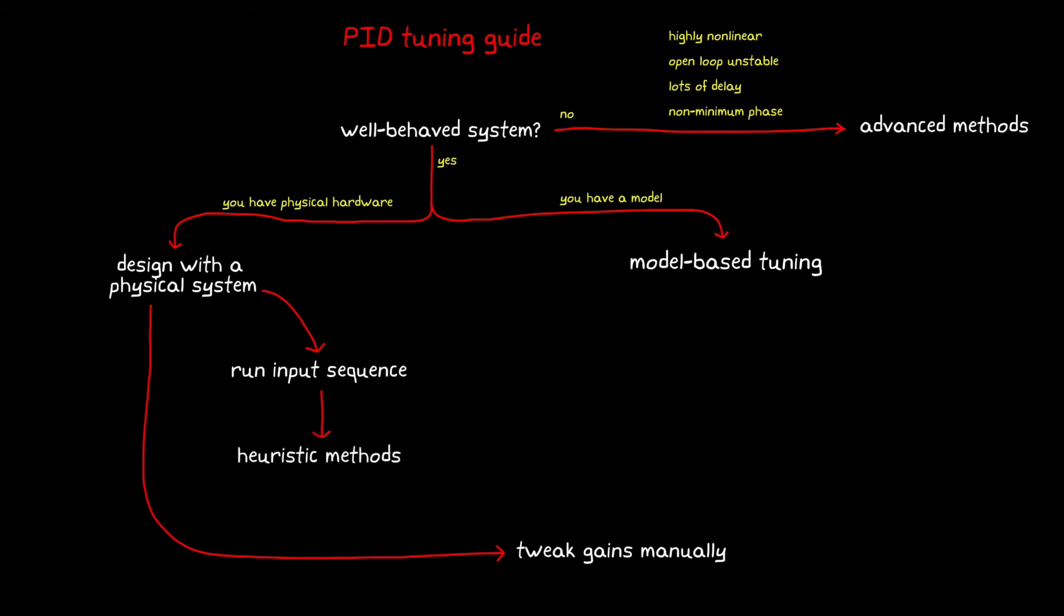From the response, you can use a heuristic technique like the Ziegler-Nichols or Cohen-Coon method. These methods are nice because you don't need a model. You just need to measure certain aspects of the response, like the time constant or oscillation period, and then use that value to calculate an initial gain set.